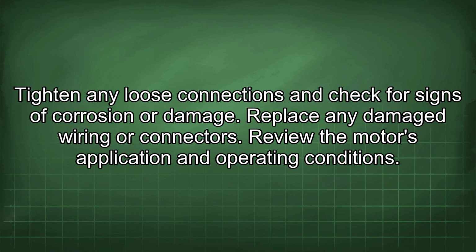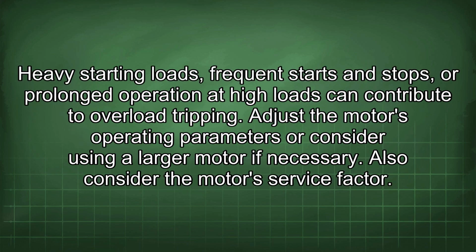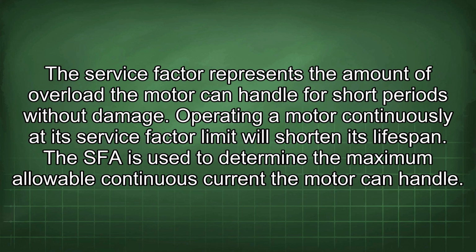Review the motor's application and operating conditions. Heavy starting loads, frequent starts and stops, or prolonged operation at high loads can contribute to overload tripping. Adjust the motor's operating parameters or consider using a larger motor if necessary. Also consider the motor service factor. The service factor represents the amount of overload the motor can handle for short periods without damage. Operating a motor continuously at its service factor limit will shorten its lifespan.